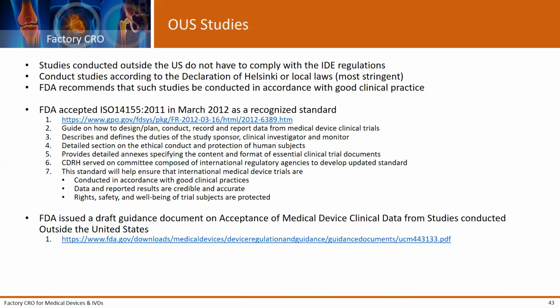So in this particular case, the company spent millions of dollars on a clinical study that showed efficacy, and all of their data was not allowed, and they were basically dropped from the FDA and told, no, you're not going to get your product approval because the investigations of adverse events was not adequate. So it's very important to make sure not only are you reporting these, but the investigations and the follow-ups are very thorough, particularly if you're outsourcing it to whoever made the device for you in our current climate of outsource everything.